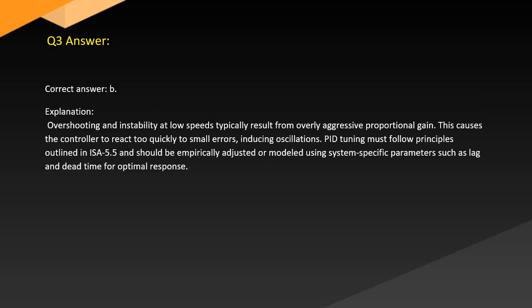Answer. Correct answer B. Explanation. Overshooting and instability at low speeds typically result from overly aggressive proportional gain. This causes the controller to react too quickly to small errors, inducing oscillations. PID tuning must follow principles outlined in ISA 5.5 and should be empirically adjusted or modeled using system-specific parameters such as lag and dead time for optimal response.